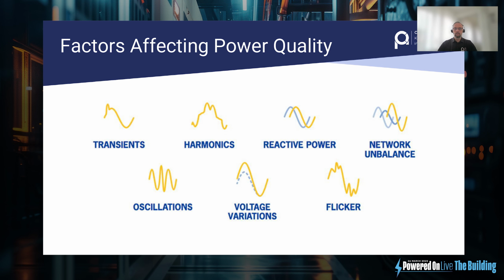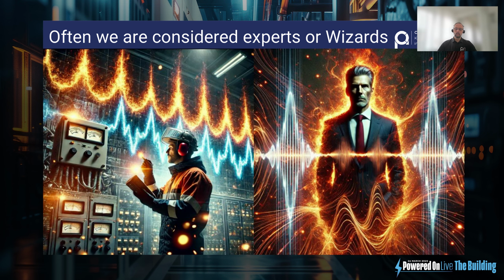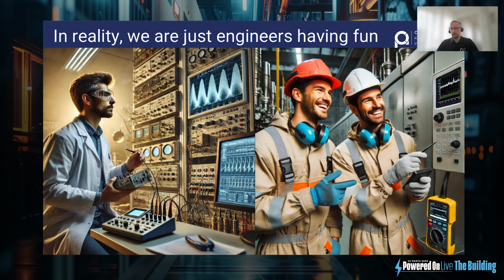So why does power quality matter? There are many factors that affect power quality, ranging from everything installed within the facility to the EV chargers themselves connecting into the power network, so to speak. Things like transients, harmonics, reactive power, network unbalance, oscillations and resonances, voltage variations, and flicker are all factors that we consider. They're the seven main key factors that affect what we consider a clean signal into the supply of your equipment or other people's equipment. In this field of power quality, we're often considered experts or wizards. A lot of people think this is crazy stuff, but the reality is we're just engineers trying to have fun and figure out what's going on when we get involved with these problems.